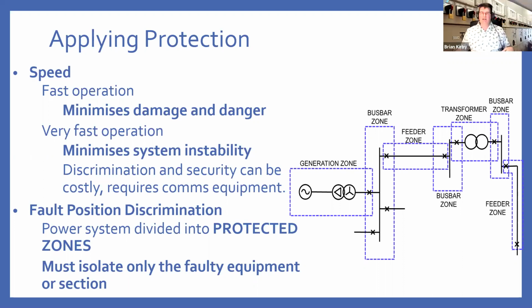What you want to do is clear the fault. If it's a transient fault, you may want to clear the fault and then reclose to see if the fault has cleared. And on transmission systems, that is quite often how they operate in the UK. You also want to discriminate where the fault has happened. As you can see on the right here, we've got various zones of protection. We have a protection zone around the generation, then around the bus bar, feeder, etc. all the way across to our final feeder, which goes out to our customers. And each zone you'll see overlaps the adjacent zones so that there are no blind spots on the network.